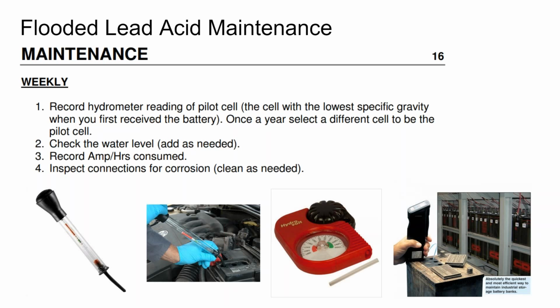That's where the maintenance starts to get a little complicated, because the cheap products for monitoring specific gravity, in my experience, require you to use the holes in the top of the battery, where the watering caps from before would fit. To stick your hydrometer down into the battery, because of the size of the tube, you've got to take the watering cap out, stick the hydrometer in, take your measurement, and then put the watering cap back in. That's what takes the most time when watering the batteries.